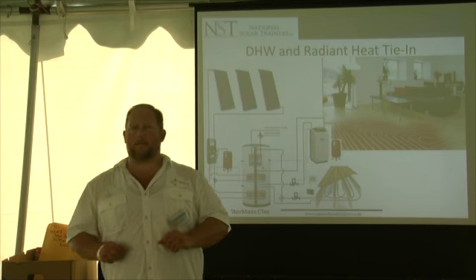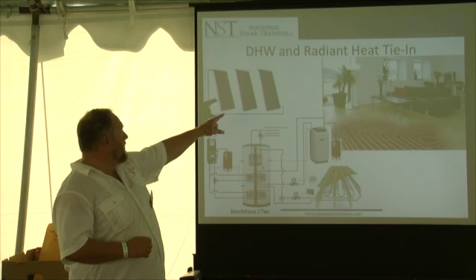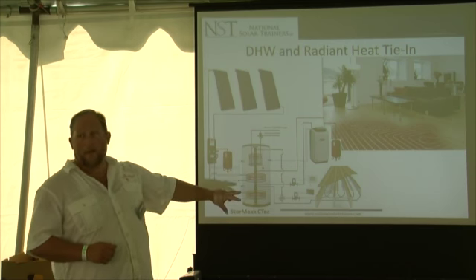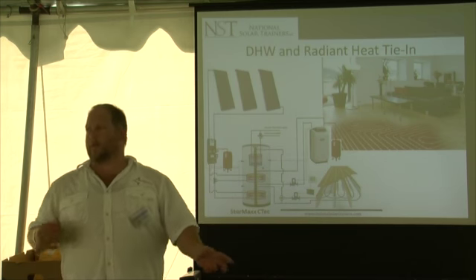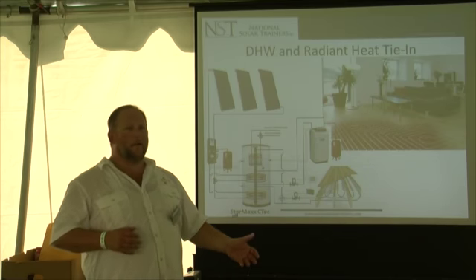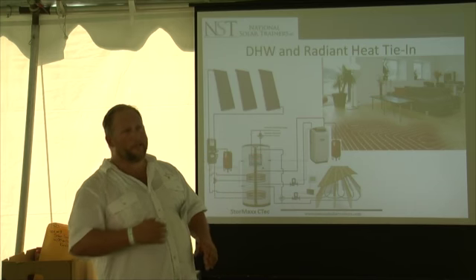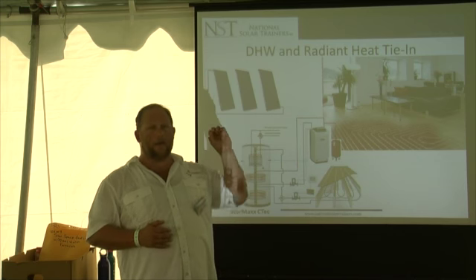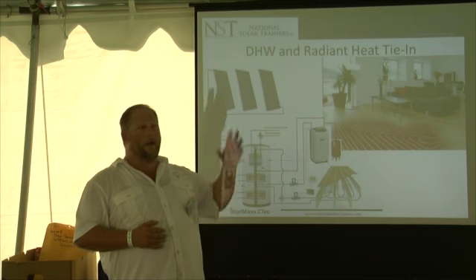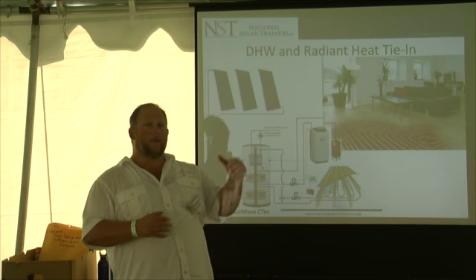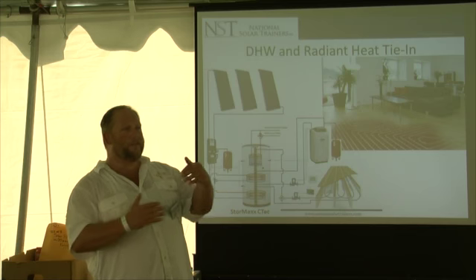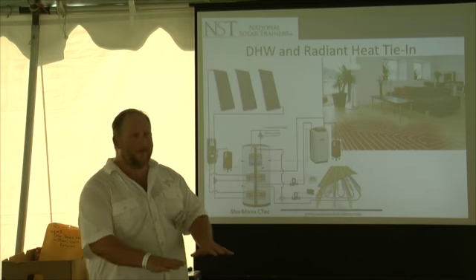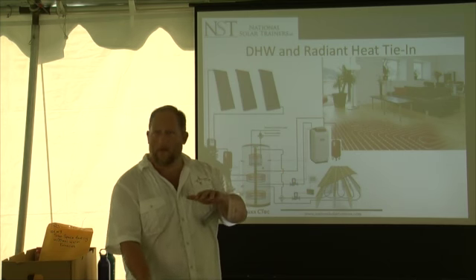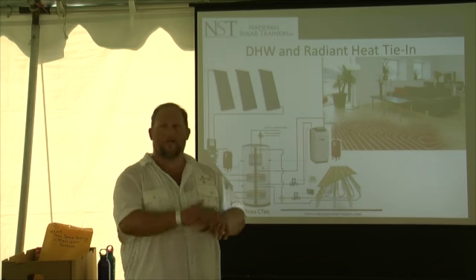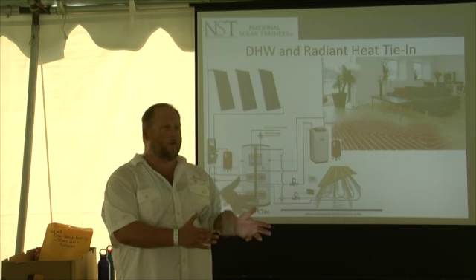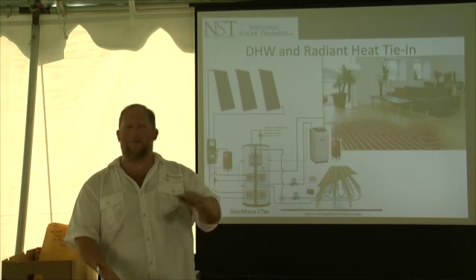Okay, so there's a lot of different ways to plumb into a radiant baseboard. This is one way. We got the collectors running into two coils on the bottom, right? This is a German method, to use multiple coils in the tank, because there are different zones of temperature inside the storage tank. They're called strata, and I want to dump into the most appropriate zone, right? I don't want a really super hot collector to dump into the coldest part of the tank, because I want it to mix with about 17 degrees less than whatever the collector temperature is. That way, at the end of the day, I still have a volume of water at the bottom of the tank that's cooler. That means that now if I charge the bottom of the tank, I can run till 6 o'clock at night rather than shutting off at 4 o'clock. You save a cold zone that you can keep putting BTUs into the tank.